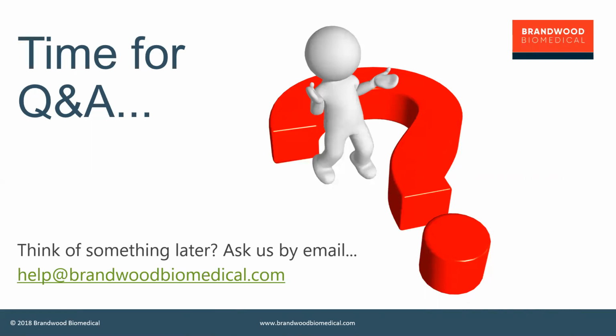And you may have had a material for 40 years. If I was to go into most manufacturers that have been around for 40 years and say, okay, show me what the material was like 35 years ago, they'd struggle to produce the records to show that. So how was it made then? How was it sterilized? What were the sterilant residues? All of that. So there's a bit of a caveat there, isn't there, about demonstrating safety of the actual finished device? There is. And I think the pet expression is the final finished device. That is the device as it comes out of the package at its point of clinical application. So that would include sterilization, and it includes the manufacturing process.